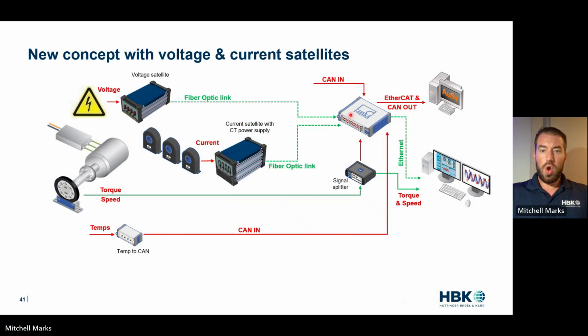So, what could be better? Well, what if we had a box that did all the digitization sitting right next to the machine? What if we had high voltage modules that were completely floating, sitting next to the machine, digitizing, and then connected to the measurement equipment over a fiber optic cable? What if the current sensors plugged into that completely isolated box, got digitized, and got sent back over fiber optic cable? This is the future that we're looking at. We're coming out with what we call our satellite modules. We have a voltage satellite, which is 4 voltages, and a current satellite, which is 4 currents. And the goal is to shorten those cables to be like 10 centimeters, as short as possible.